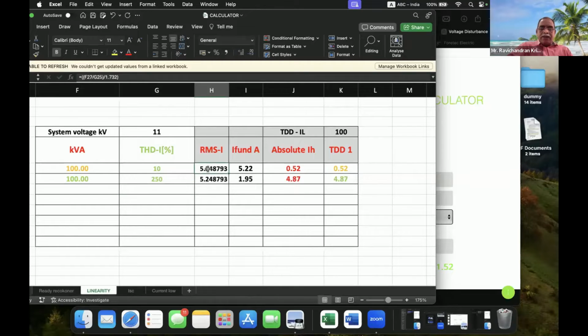See, this RMS current is the same, but the fundamental current differs. From the absolute harmonic current, for this 100 kVA load at 250% THD-I, the absolute harmonic current is 4.87 amperes. On the other hand, at 10% THD-I, it is only 0.52 ampere absolute current.